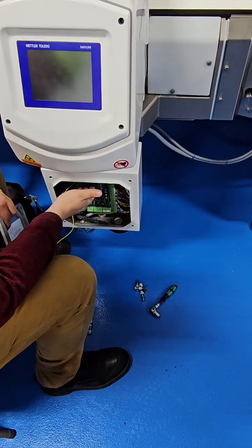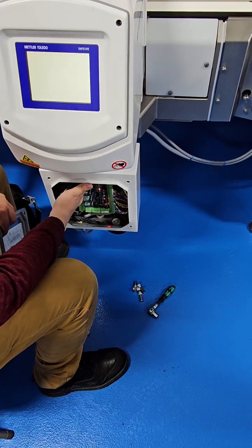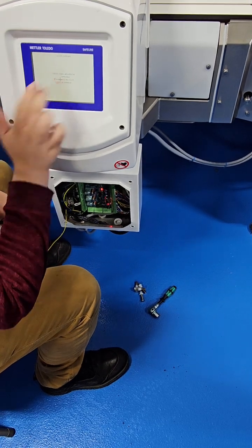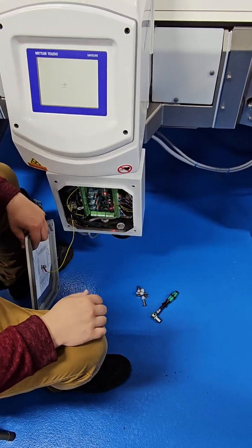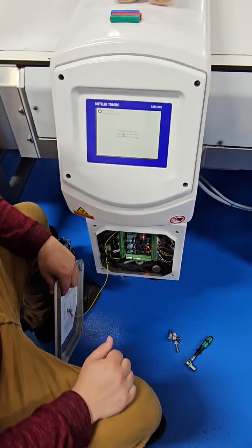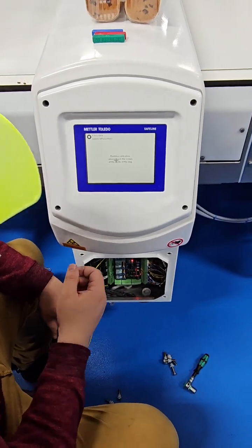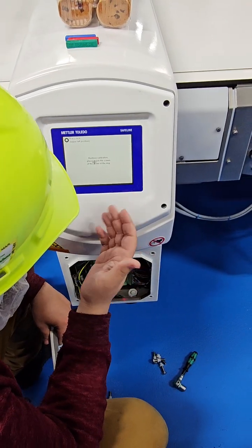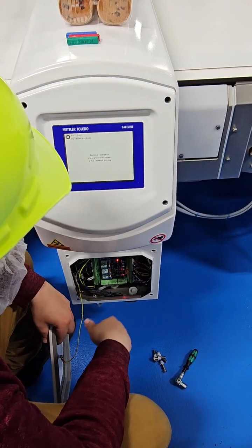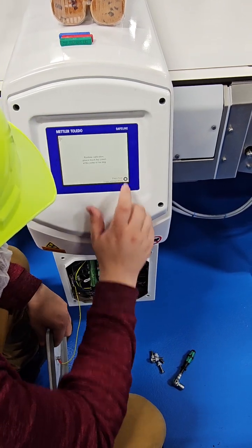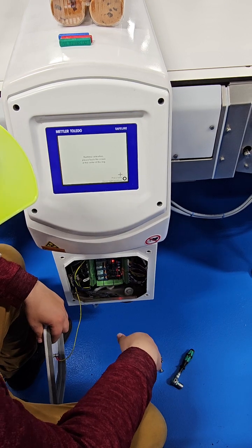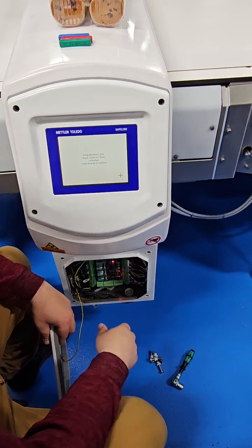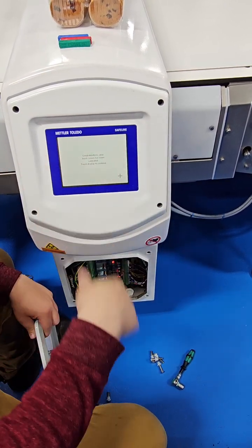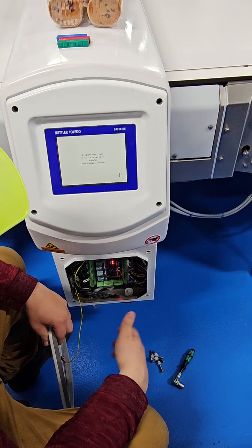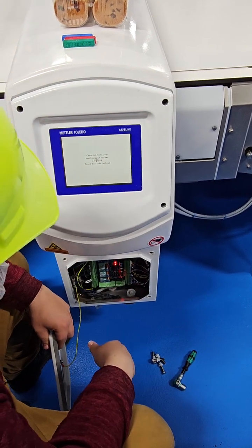The way we calibrate the touchscreen on this machine is we turn it on and touch the screen. Before the system boots up, turn it on, touch the screen, and follow the on-screen instructions: please touch the screen at the center of the ring. Even though it was already not quite calibrated right -- you see where I touched it, the X didn't appear -- now the calibration is complete.